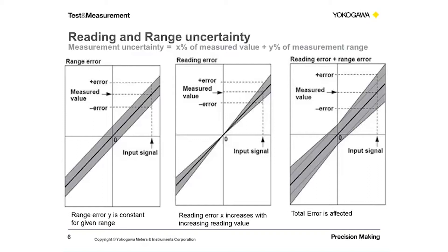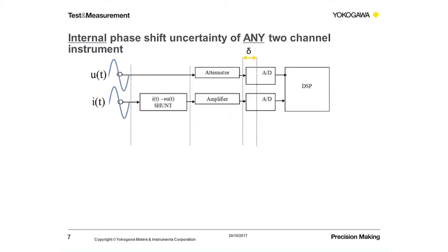Phase shift uncertainty — is that related to power factor? It's more or less related to power factor. Power factor indicates something about the signal. Whenever there's a phase difference, that will have an impact on the power reading. AC power is the contribution of voltage, current, and the phase shift between them. However, every two-channel measurement instrument will introduce a phase shift on the input signals by themselves, mainly due to the difference in the input circuits between voltage and current. High-speed data acquisition instruments with only voltage input will also be affected by this.